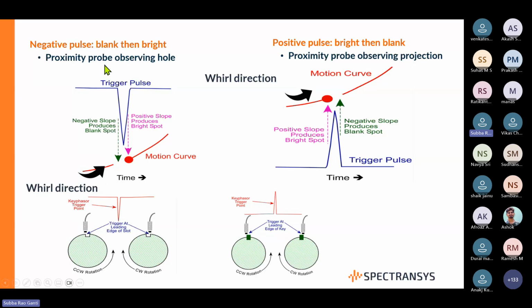When the proximity probe is observing a hole or a keyway, it is a negative trigger pulse. When the negative trigger pulse comes up, initially you will have a blank and then the bright, and the movement of the shaft center line or the direction of precession is in this way - in this clockwise direction.